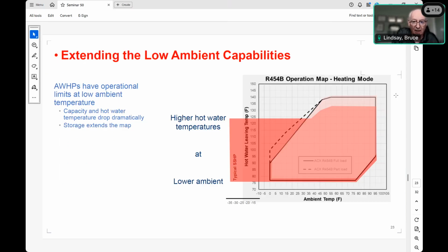Here's the real beauty that I'm going to talk about. What you see here is an operation map for a heat pump in a heating mode. At 95 degrees ambient temperature, we can supply 140-degree hot water to the building. As the ambient temperature drops down to 47 degrees, at 47, we start to see a derating, a capacity loss. And as you go all the way down to 0 degrees, you can see you can only produce 90-degree water. That might be useful, but that's awful challenging on existing buildings.